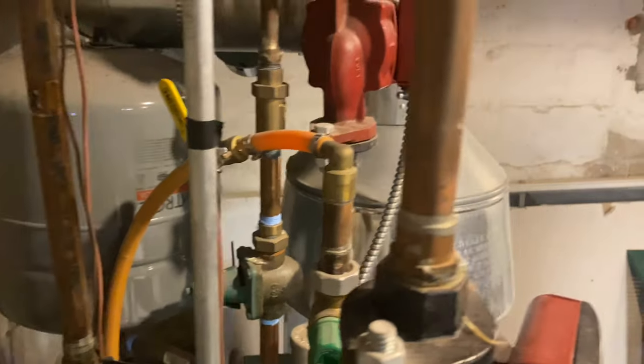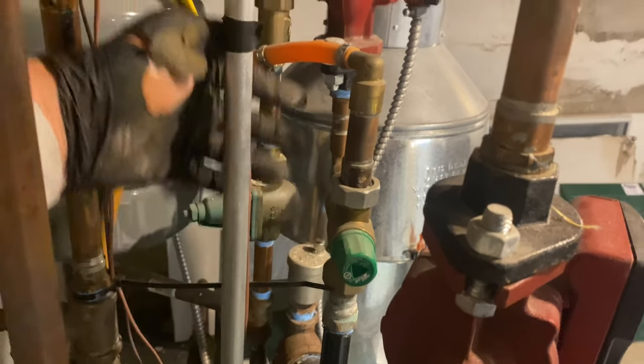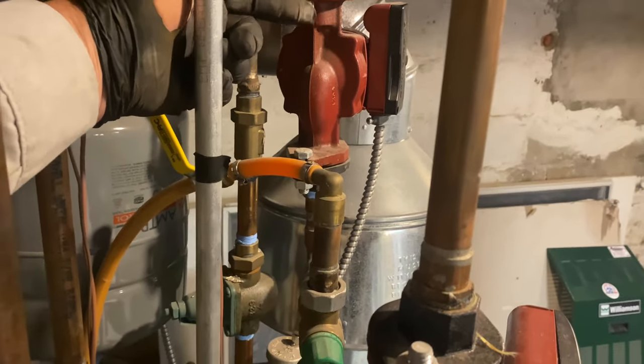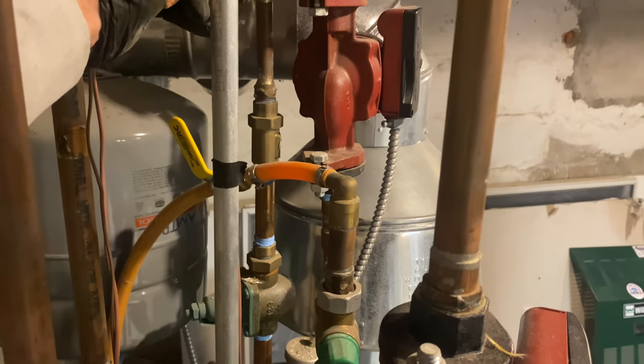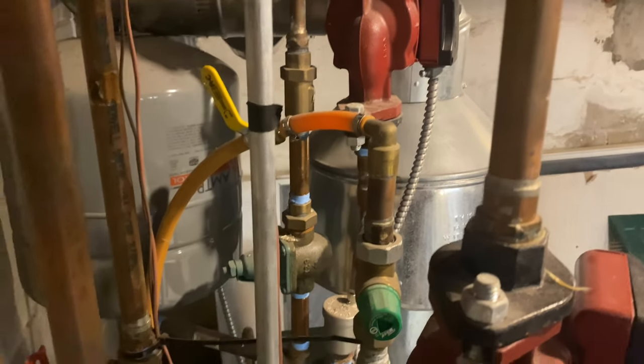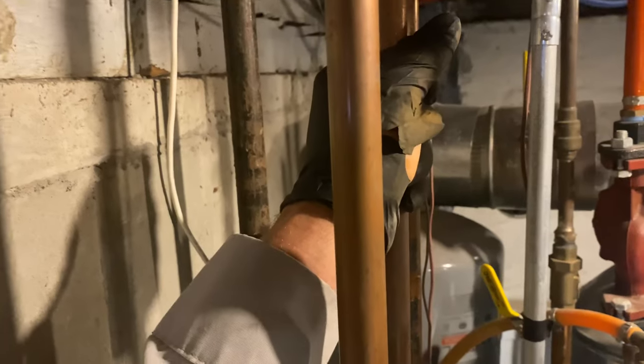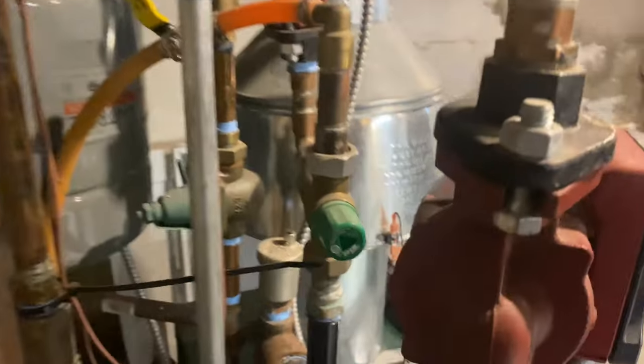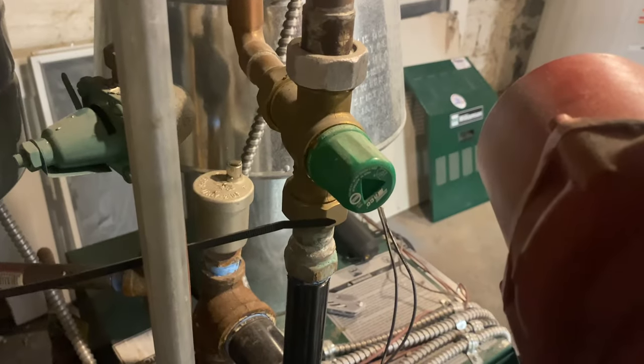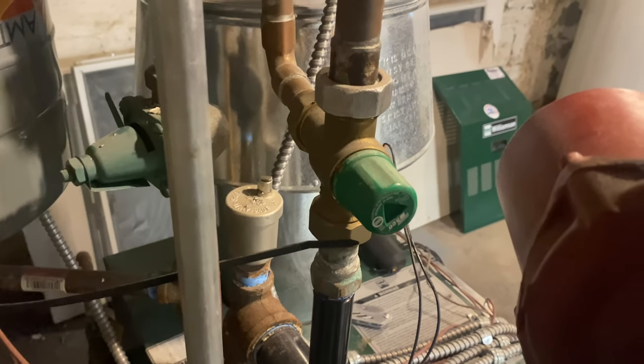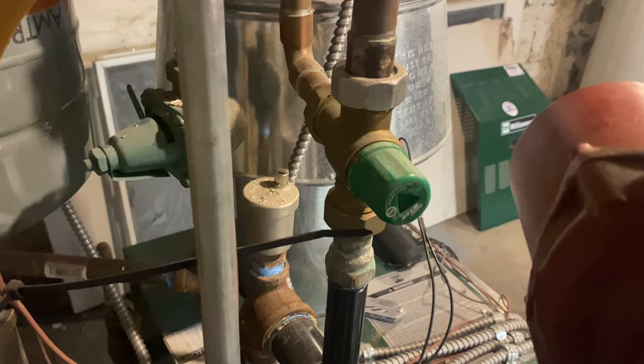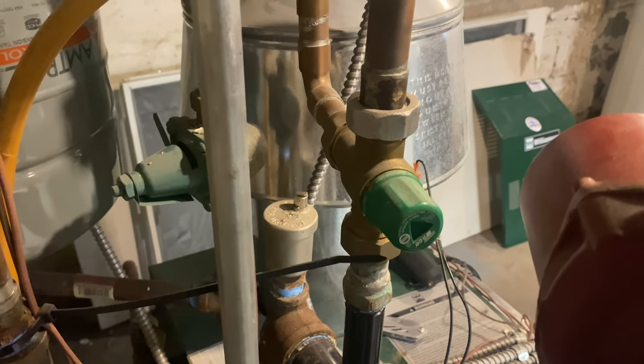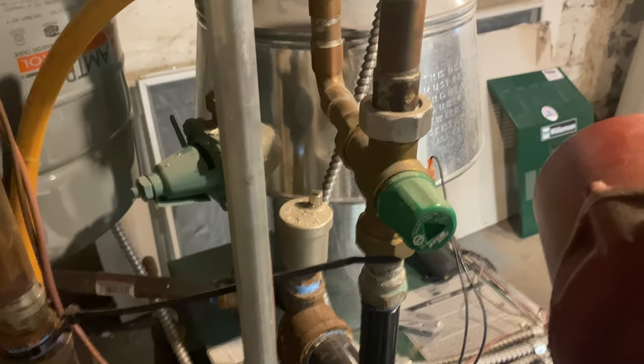No, I'm just speaking in general terms, because this is a mixing valve, a thermostatic mixing valve, which just needs to send lower temperature water than the boiler normally creates to that floor. Right, I know, but hypothetically speaking, if they did have a wooden floor, you want to make sure that mixing valve is doing its job, that the floor doesn't get too hot. They would tell you, but since they couldn't walk on the floor, that'd be the first symptom—the floor is burning hot. You see that? Yeah, it happens.